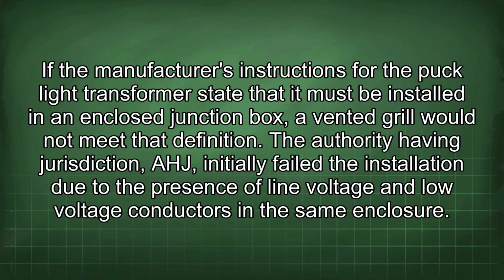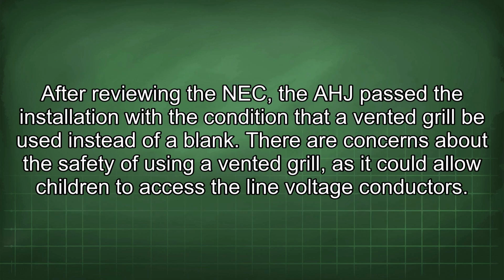If the manufacturer's instructions for the puck light transformer state that it must be installed in an enclosed junction box, a vented grill would not meet that definition. The authority having jurisdiction, AHJ, initially failed the installation due to the presence of line voltage and low voltage conductors in the same enclosure. After reviewing the NEC, the AHJ passed the installation with the condition that a vented grill be used instead of a blank.